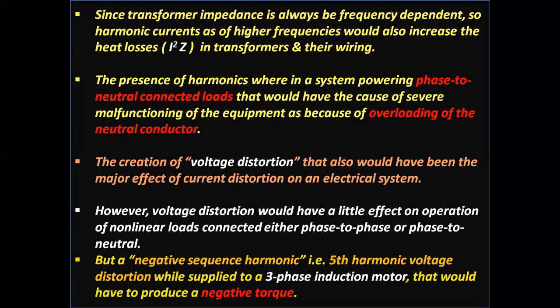The creation of voltage distortion is also a major effect of current distortion on an electrical system. Voltage distortion has little effect on operation of nonlinear loads connected phase-to-phase or phase-to-neutral. However, a negative sequence harmonic — that is fifth harmonic voltage distortion — when supplied to a three-phase induction motor, would produce a negative torque.